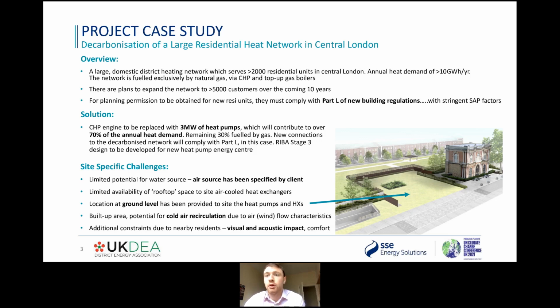But we were given a plot of ground at ground level, which we've been told was where we had to site the heat pumps and the heat exchanger. So we've had to deal with that, which is a bit of an issue. Obviously it's a very built up area that we're dealing with. There's some residents very nearby. There's one domestic property basically right beside the plot of land that we've got there, so those air chilling and cold nuisance and visible plume issues were obviously going to be pertinent in that scenario.